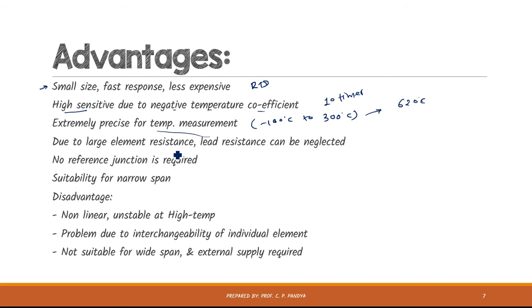Due to large element resistance, lead resistance can be neglected. Okay, so lead resistance will not create any errors inside of the reading. No reference junction is required as in case of thermocouple. Then it is suitable for narrow span temperature measurement as I said.